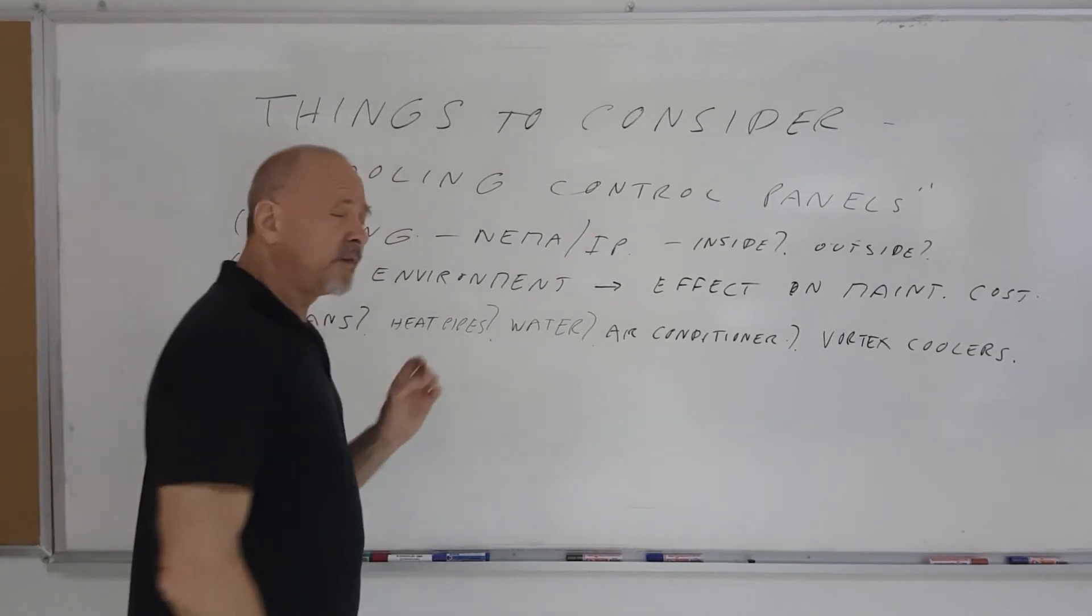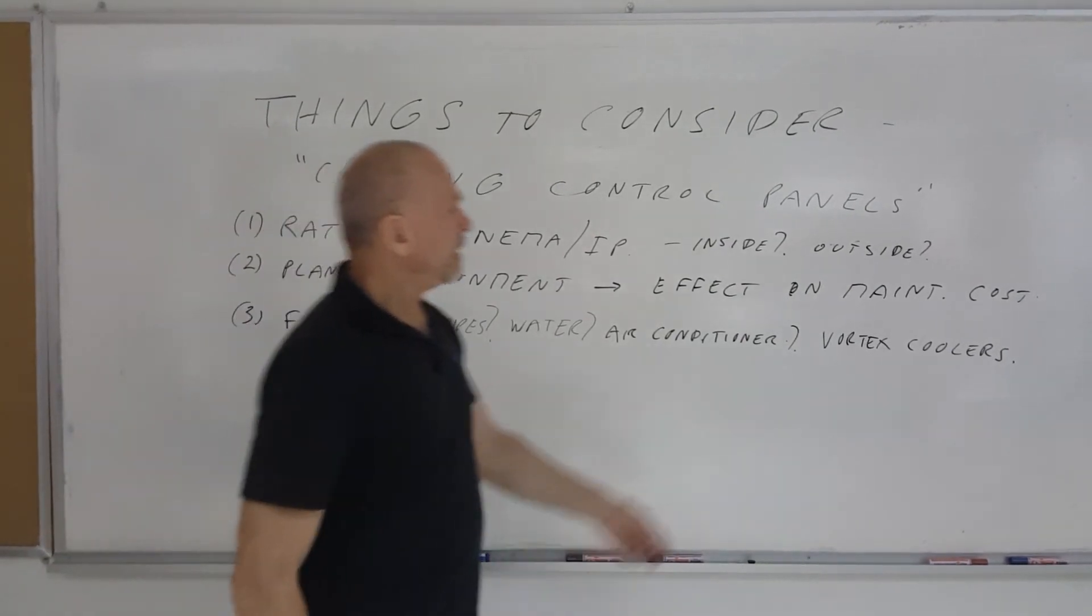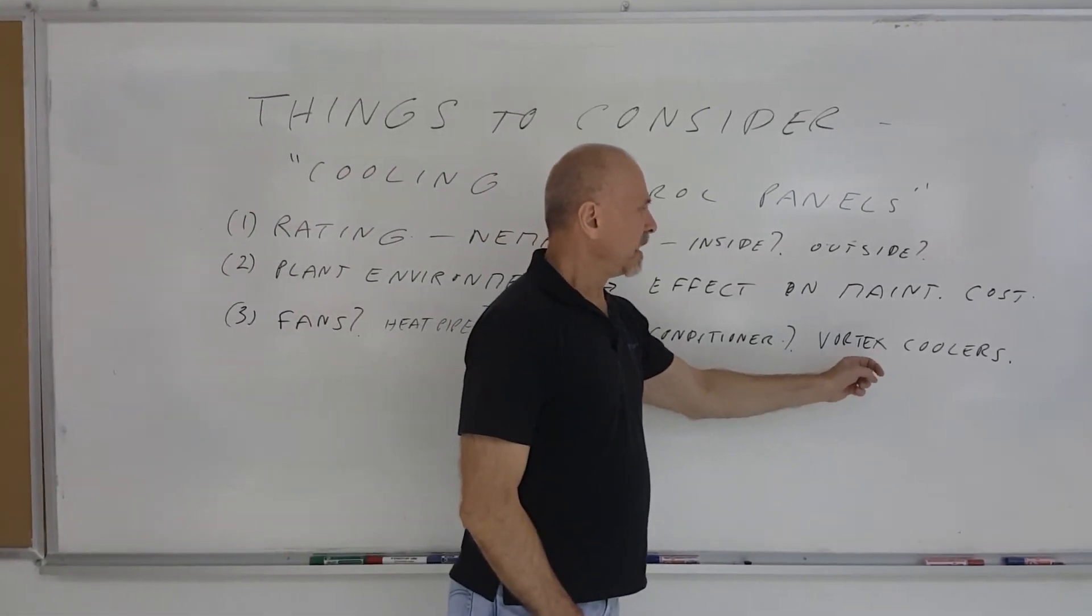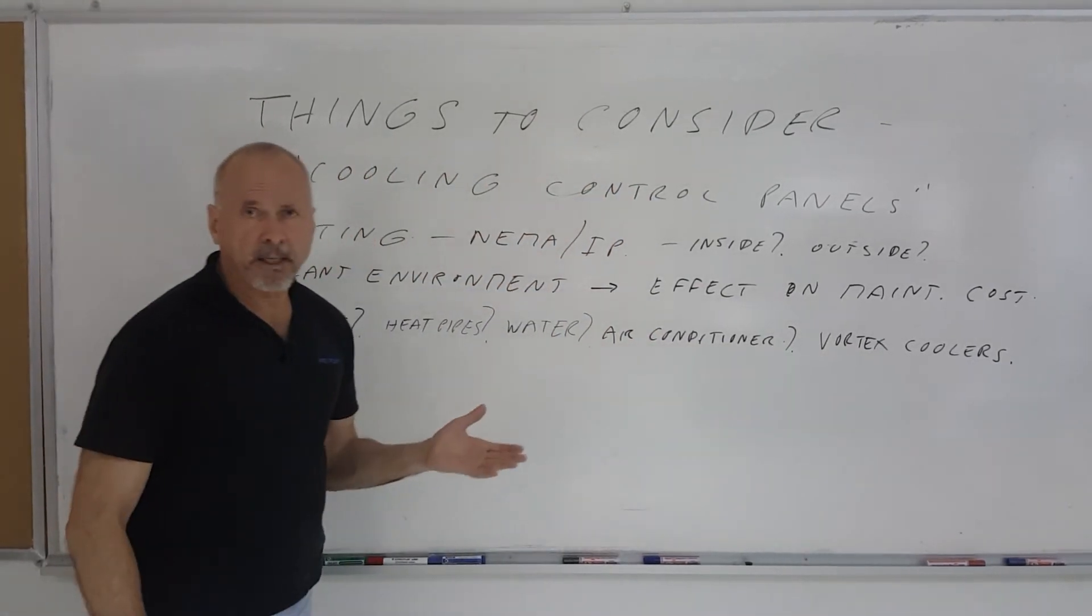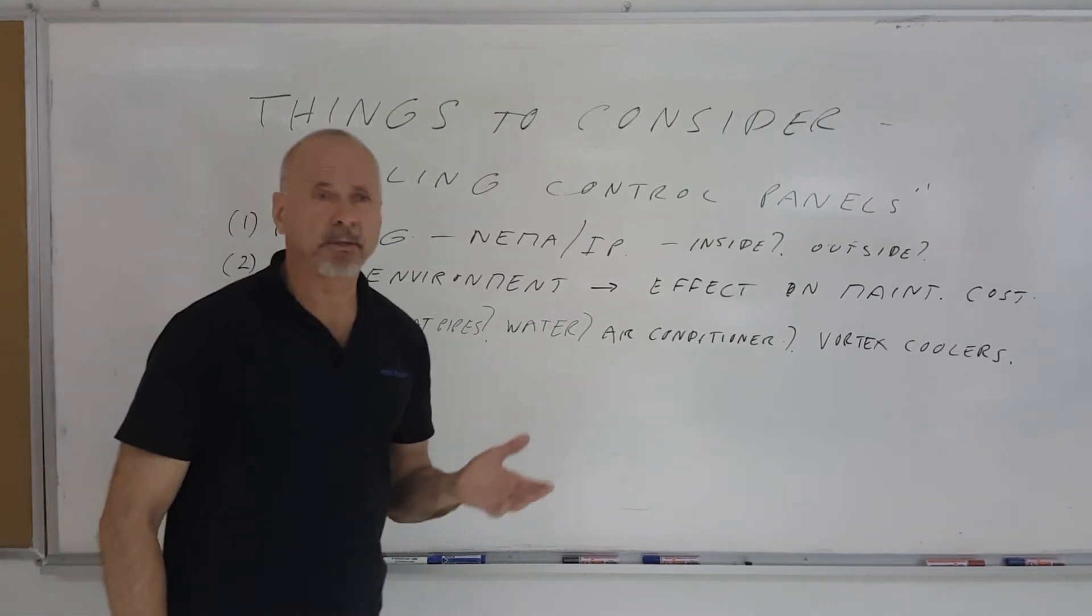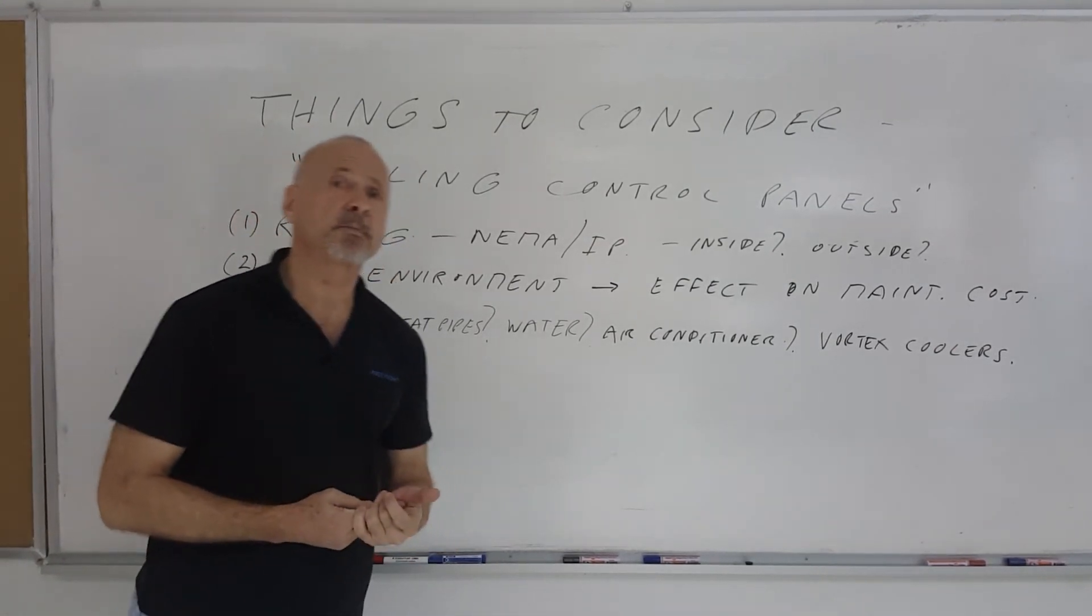So when you get to a very dirty environment, you then have to really consider using compressed air operated vortex coolers. The vortex coolers have virtually no maintenance. They're not subject to vibrational damage, no chemicals, no condensate produced.